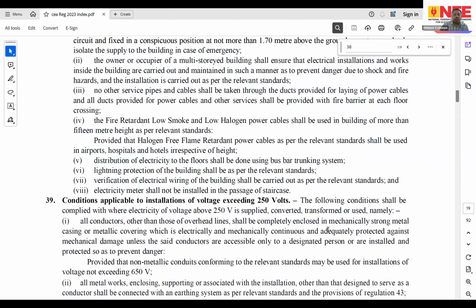So you can imagine the voltage drops as well as the cable losses that could be present in it. Now, when it comes to having bus risers, rising mains, the voltage drops can be reduced to a much, much lower level. I think in NEC, it is specified that from the point of supply to, let's say, the end point of a lighting circuit or a power circuit, the voltage drop needs to be regulated to about 6%. And such voltage regulation would not be possible in a high rise if you're going to take cables from downstairs to upstairs. Hence, the regulations talk about rising mains using a bus bar trunking system.